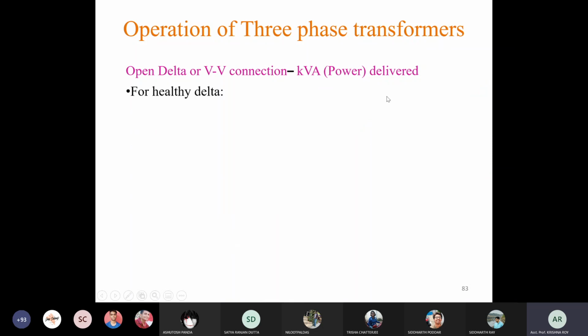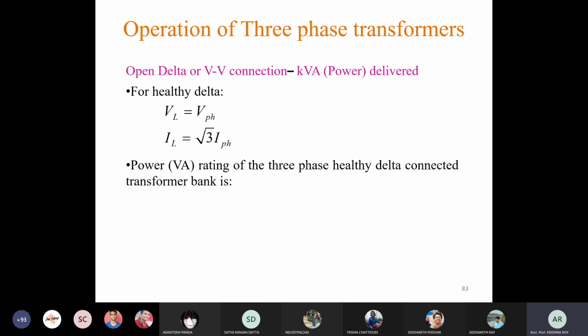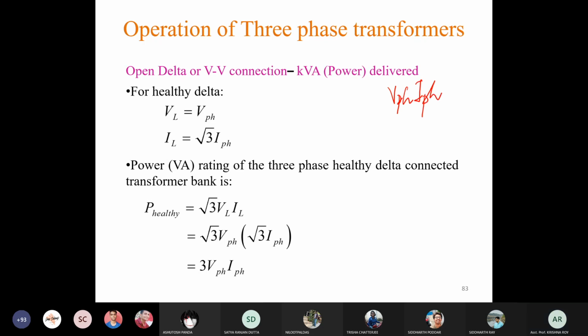Let us see. For a healthy delta, that means a proper delta connection, VL equals V phase, we know, and IL equals √3 I phase, that we know. Therefore the total kVA rating of a 3-phase delta connected bank will be √3 VL IL. So this is the capacity of a 3-phase bank connected in delta. This is P healthy, that is equal to √3 VL IL, and putting the values of IL and VL, we get 3 V phase I phase. That means 3 into the capacity of each transformer. Capacity of each transformer is V phase I phase. So if we multiply it by 3, we will get the total capacity. As simple as that.